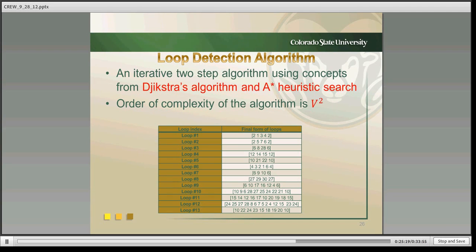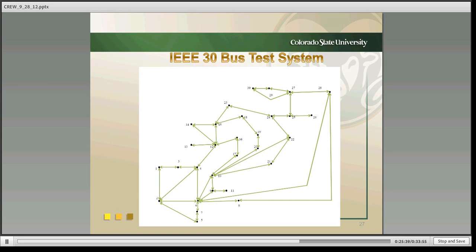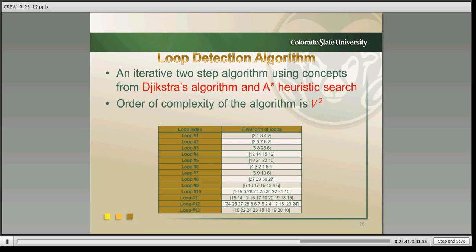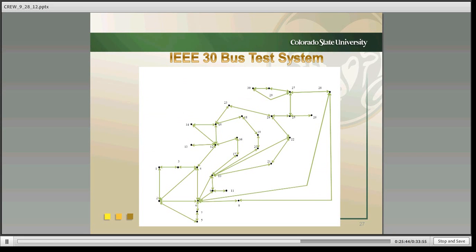If the donut has a steel ring on the inside, you just start eating the donut from the periphery, and in the end you're going to be left with the steel ring inside. That's essentially what the last loop of this algorithm is. That was something really fascinating for us, and I'm going to highlight that particular loop here. So the loop we detected in the end was right here: 10, 22, 24, 23, 15, 18, 19, 20, and back to 10. This is sort of the innermost link graphically for this particular power system network.